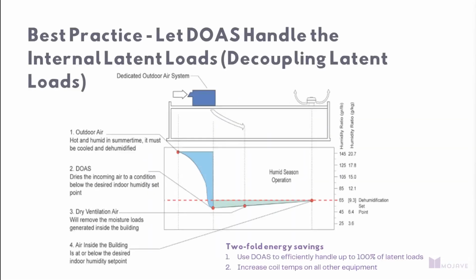To start off, there is a best practice piece that I'd like to touch on. This is right out of an ASHRAE design handbook. It is best practice when you're designing around DOAS systems to push your discharge dew point out of the unit a few degrees lower than your zone condition. And the reason for that is if you're discharging, say you need 55 dew point in zone, if you discharge at 55 dew point right out of your unit, you assume zero infiltration in your space, and that's just simply not going to be the case.